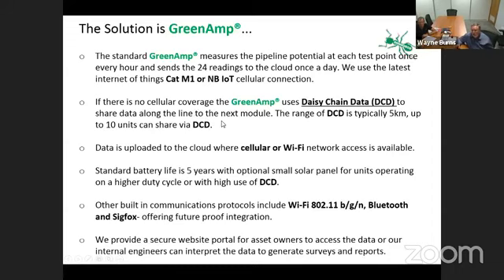The green amp uses something called daisy chain data. It collects the data at each test point and sends it to the adjacent green amp system or test point, daisy chaining the data down until it finds an outlet it can send out through, such as a Cat-M1 network or similar. Typically we go 5 kilometres between test points, though we've gone as far as 10 kilometres in fairly rugged country and still got data transmitting. We try to restrict it to no more than 10 daisy chain links, simply due to data transmission time. The intelligence of the green amp daisy chain system is such that it waits for one transmission to come through, then sends two, then three, then four.